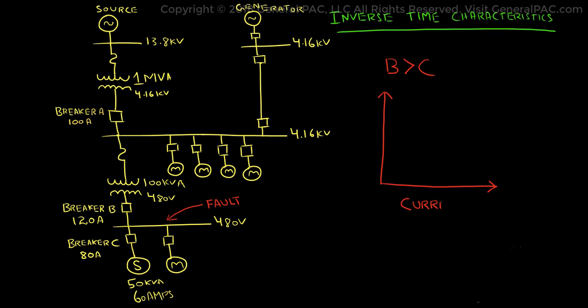We have the current level on the x-axis, and the trip time on the y-axis. For the same value of fault current, the upstream breaker B will have a higher delay time than the downstream breaker C. This is due to the shift in the curves. Breaker C picks up at lower amp rating, while breaker B picks up at a higher amp rating. This is one way to achieve coordination by using inverse time characteristics of the breakers and the breaker amp ratings.